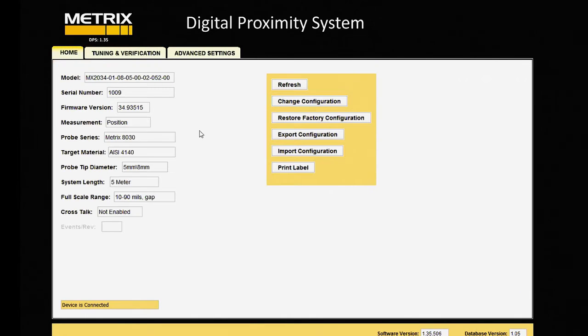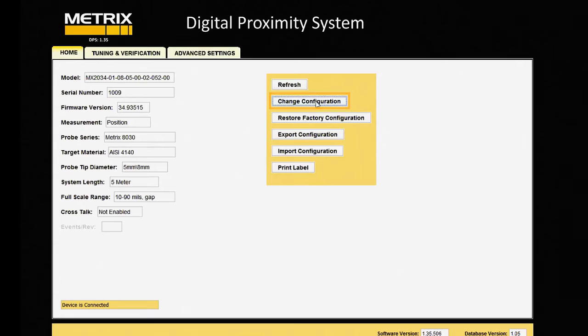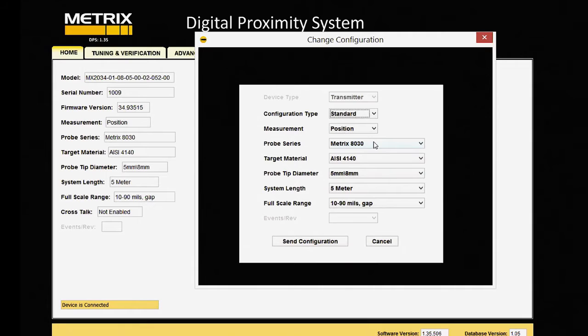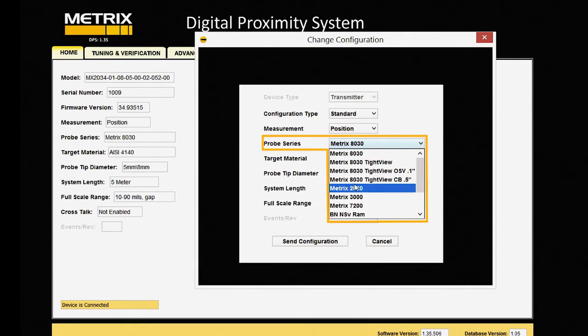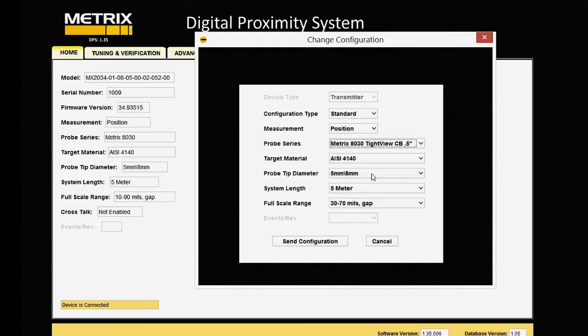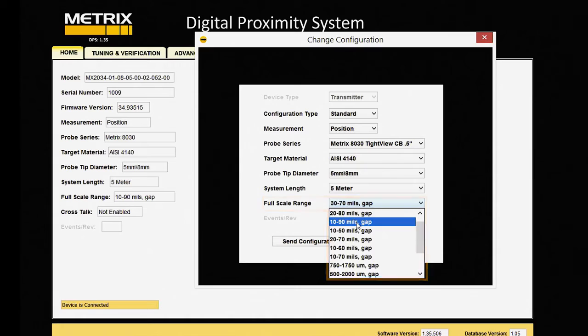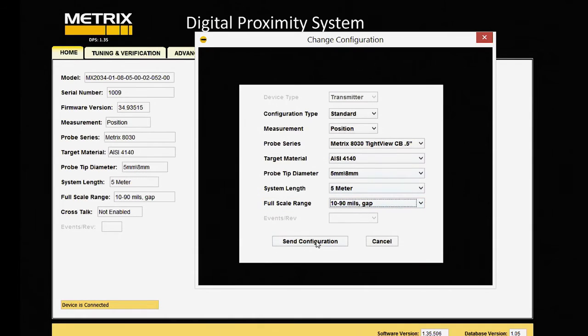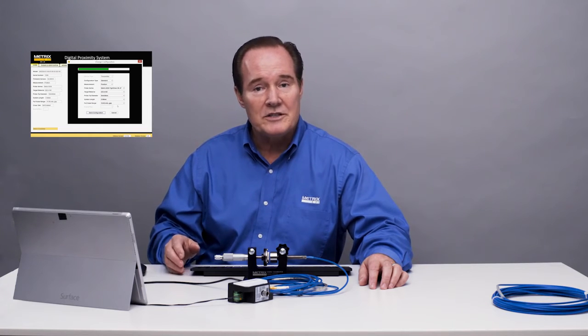So we're going to go back to that home page, and we're going to reconfigure it for TightView, and that's what I'm going to go ahead and do right now. So we'll go to the probe series, and we'll select MX8030 TightView, and we'll pick counter bore, and we'll go 10 to 90 still on the range. Everything else remains the same, still a 4140 target, and we'll send the configuration. Then after we send this configuration, we'll do a verification to see if everything is linear, or to see if we've made an improvement.